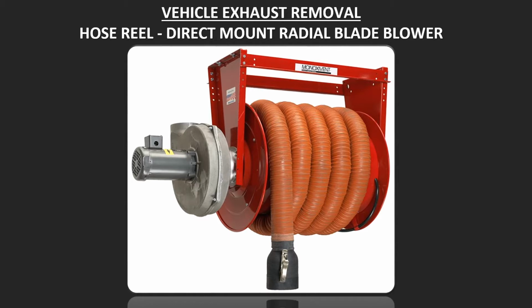Another thing we can do is you don't have to mount the fan directly on the hose reel. Let's say we have an application with 5 hose reels and 1 central fan. We can put that DMSHR switch on all 5 hose reels and daisy chain them together, so that when the first hose reel's hose is pulled down the fan starts, and when the last hose on the hose reel is recoiled, the fan turns off.